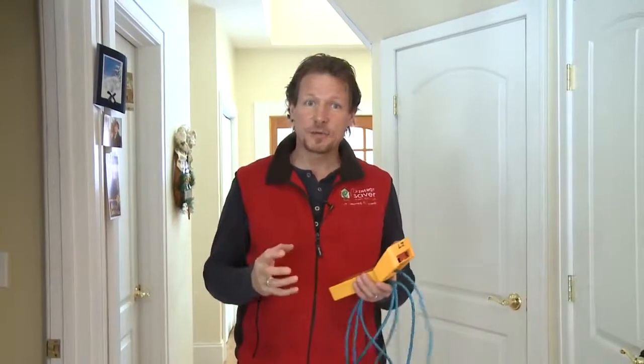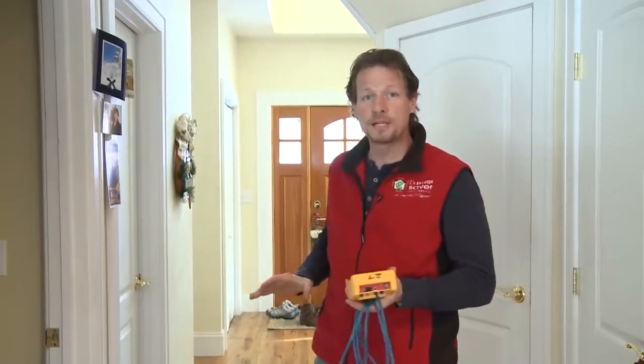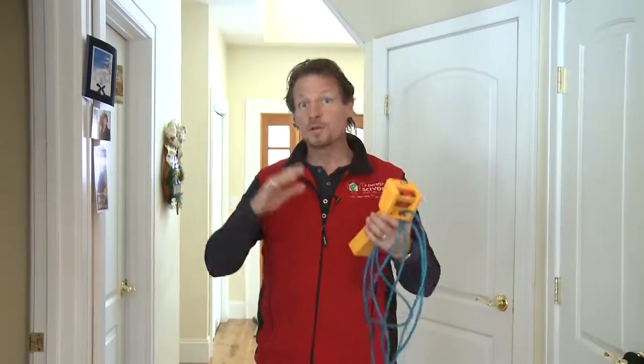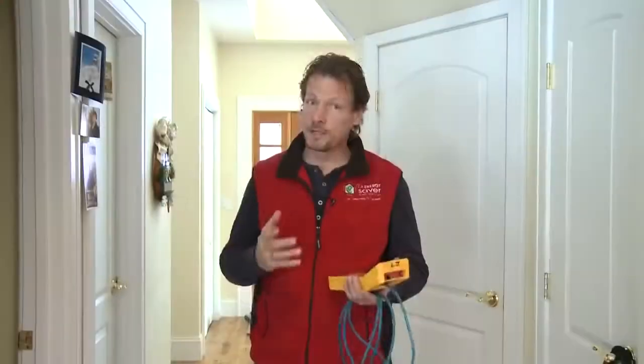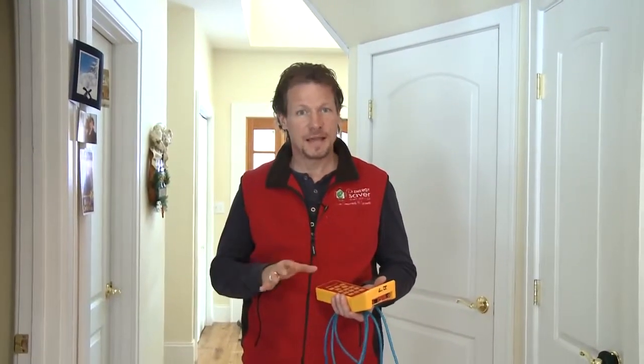At Dr. Energy Saver, we do a blower door test to quantify the total air leaks in your house. The blower door exaggerates the air leaks that are in your house, and it puts all that leakage in one place where we can measure it and compare it to a standard that the Department of Energy uses to calculate whether a house leaks more air than it should. When the blower door test is running, all leaks are created equal, but we know that when the blower door is taken away, and that's how you live, you don't have a blower door running all the time, that this, what we've shown you in this video, is how a house really works. So we want to focus on the top of the house first, the bottom of the house second, and the middle of the house last.